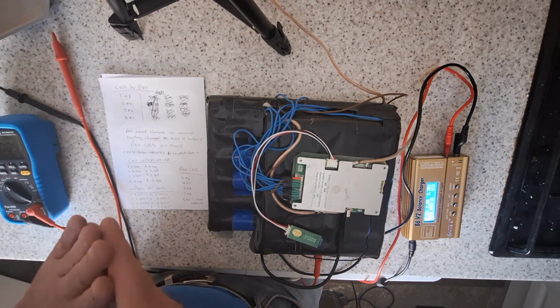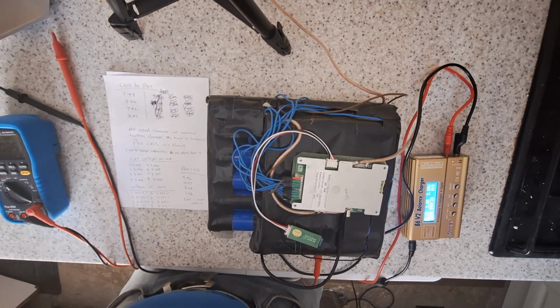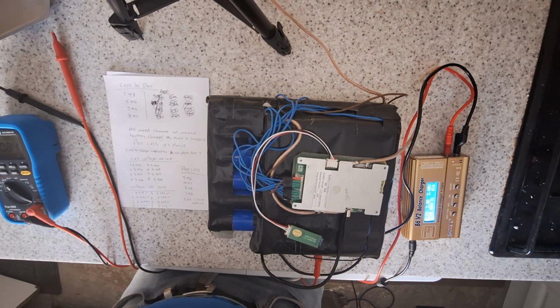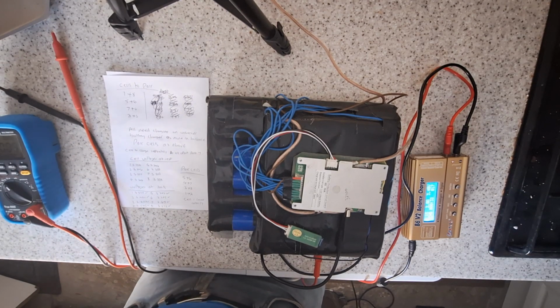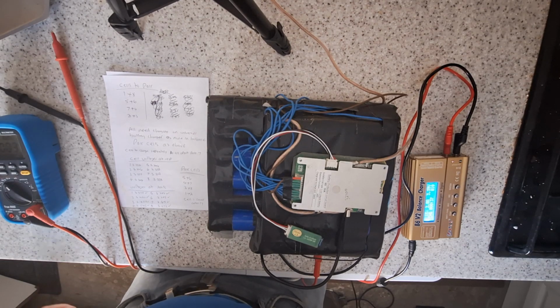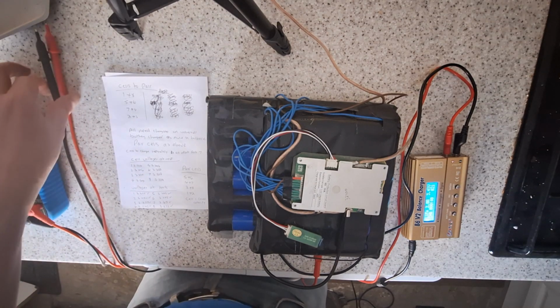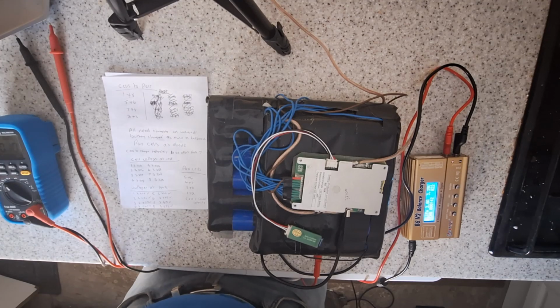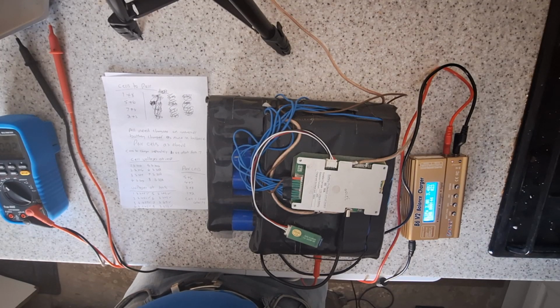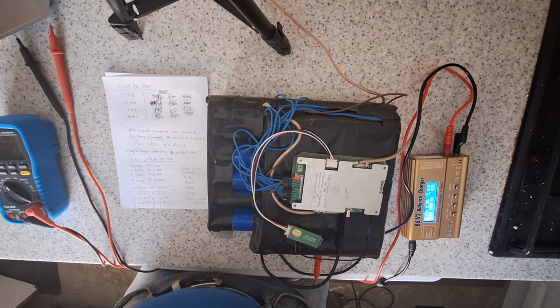Obviously you don't want to pair a battery that's weaker than the other, because it will cause high currents to flow. If one cell is discharging and the other is charged, they must all be the same voltage, same capacity, give or take a small amount of capacity, perhaps 250 milliamp hour or so, and they need to be the same in series resistance as well.